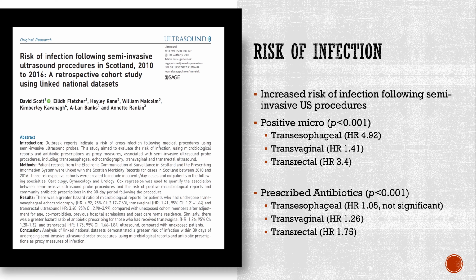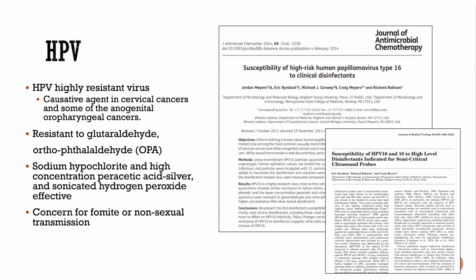So a little bit about HPV. It was recognized that they are resistant to glutaraldehyde, and this had been a pretty common agent to disinfect our probes that we were using. Many of you may have been in OB wards or units and seen the little holders hanging on the wall of the utility room, where they were using the OPA to disinfect.